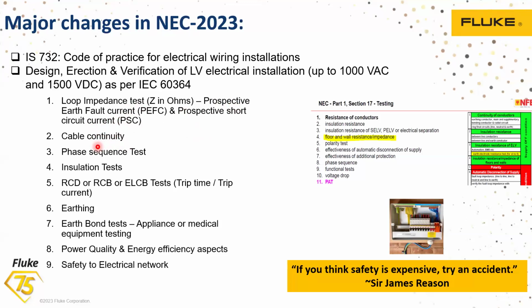In a multimeter, what happens? The multimeter acts as a load when you're taking the measurement, but for cable continuity, the tester has to inject some amount of current to measure the continuity. I'll be showing that in the coming slide, how much current it is. Then also the phase sequence test. See, phase sequence, RYB, from your electrical panel till the load side, the sequence should be properly connected.